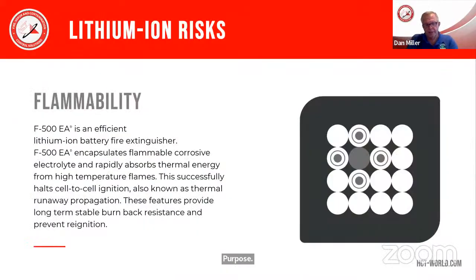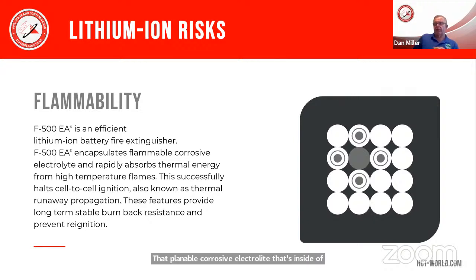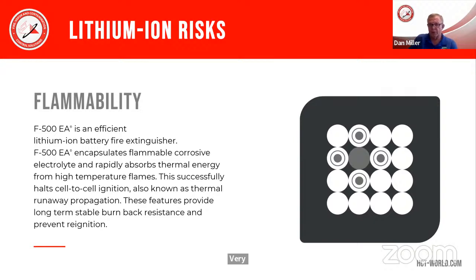So lithium-ion batteries, obviously a flammability hazard. That flammable, corrosive electrolyte inside of those batteries—because of different misuses, misapplications, or trauma—goes from cell to cell to cell. It propagates, the thermal runaway does, and F500 is able to get in there, penetrate not only between the batteries in the battery pack, but into the layers inside of the batteries, especially where they've started to come apart due to overheating. It gets in, penetrates quickly, cools everything down much more quickly than plain water. It encapsulates those hazardous off-gases and stops the incident very, very quickly, typically within just a few seconds, if you're applying it appropriately and with enough volume.